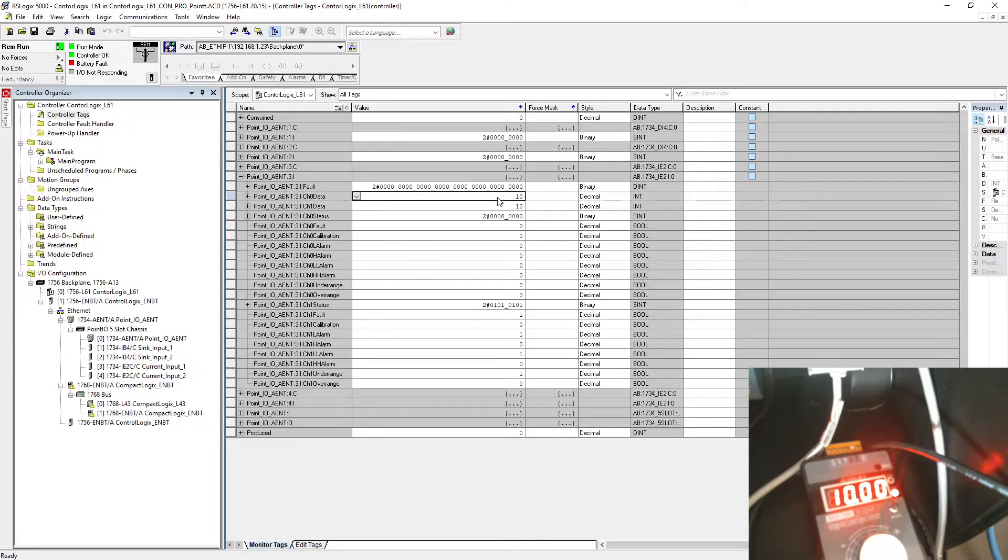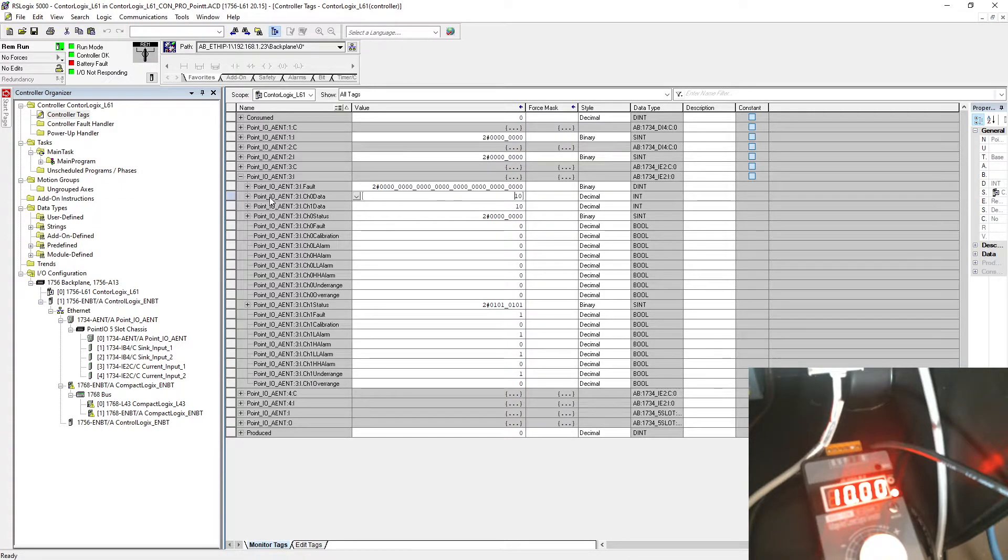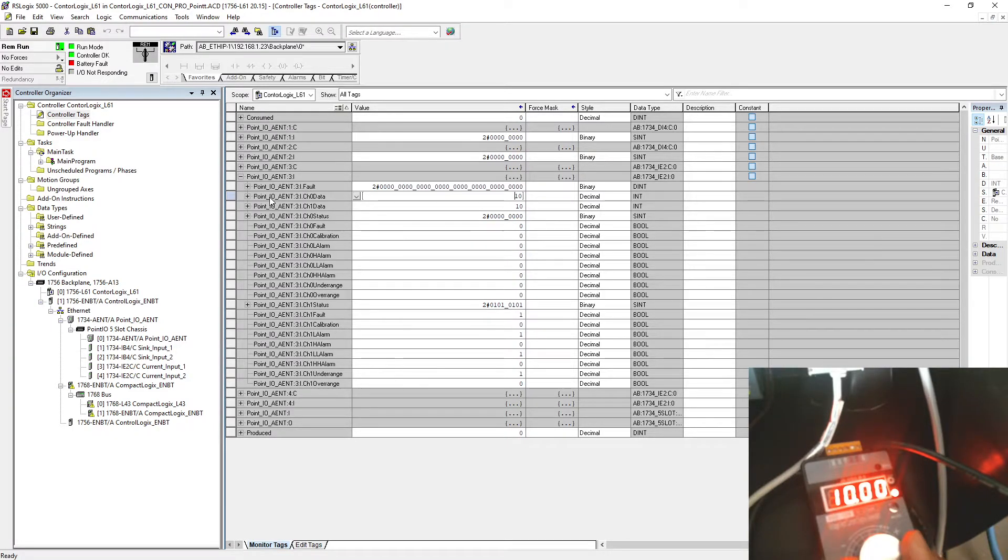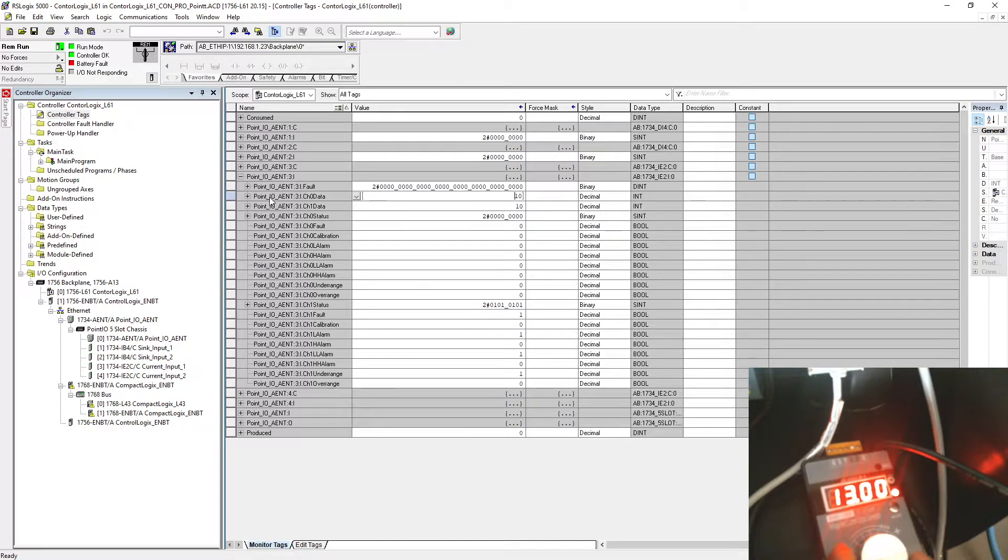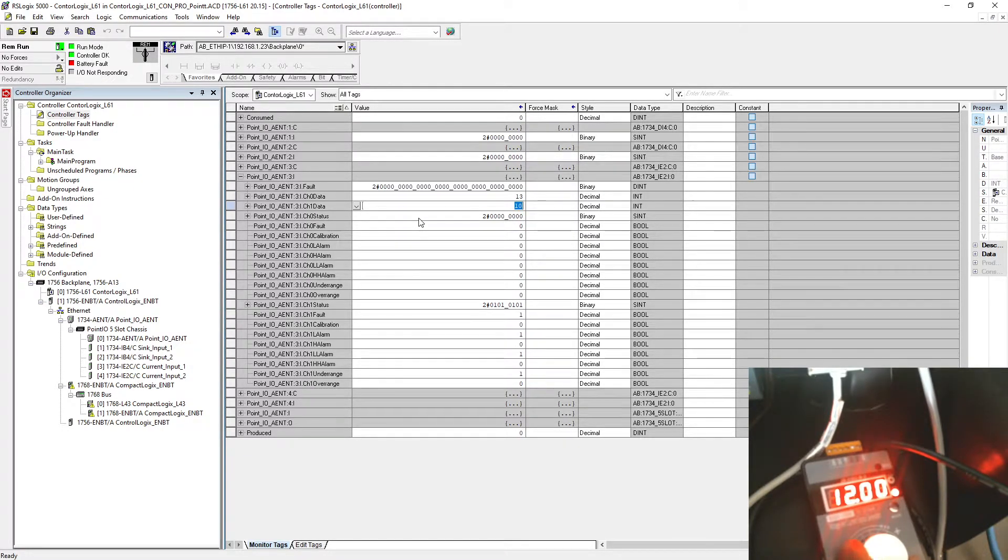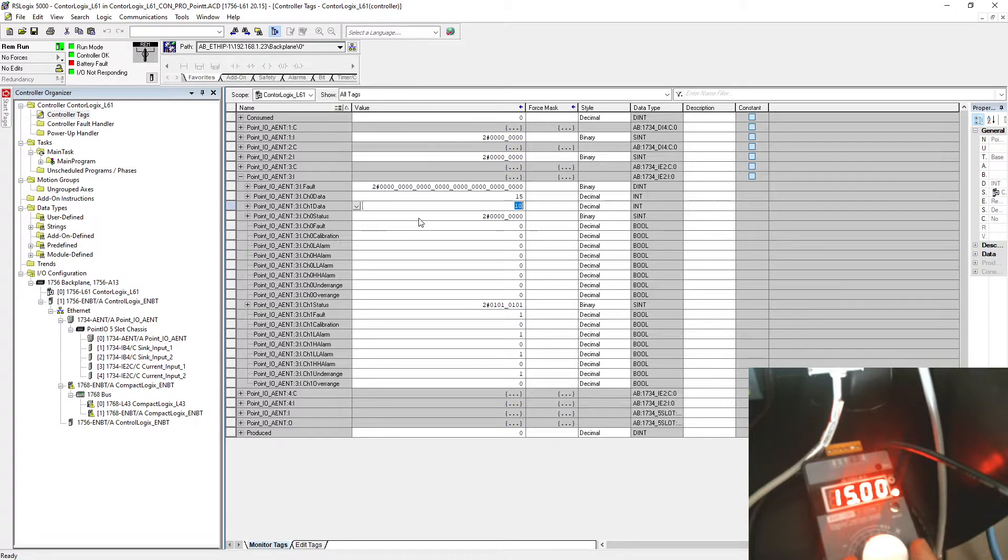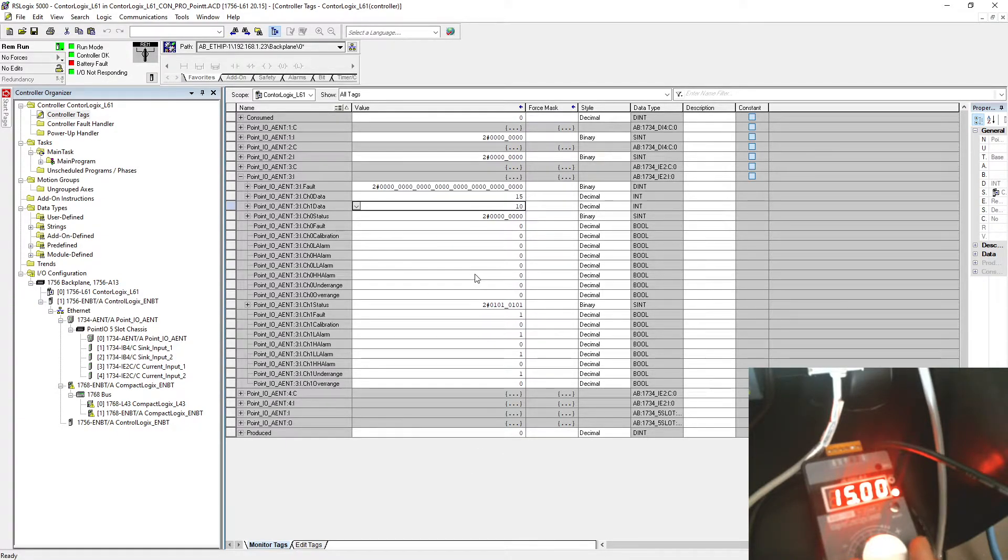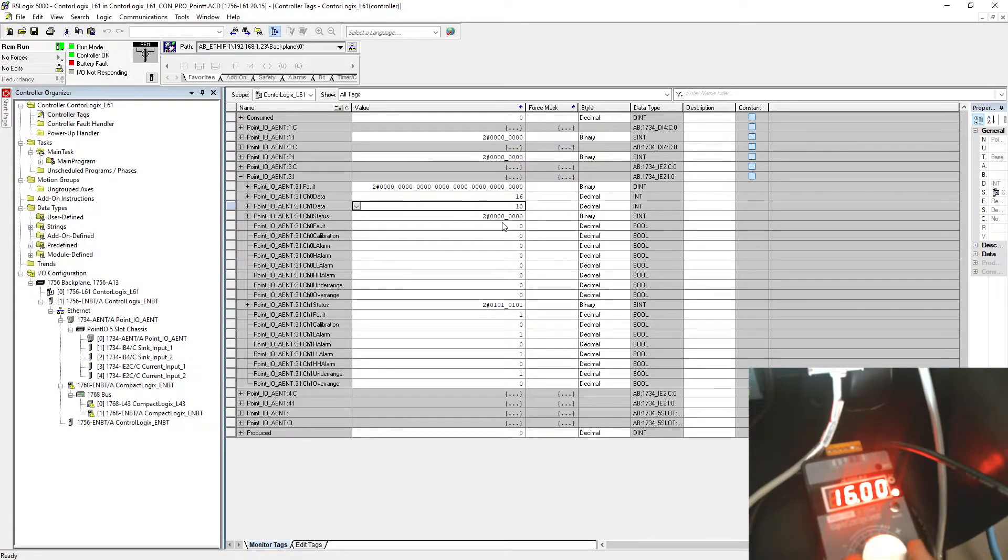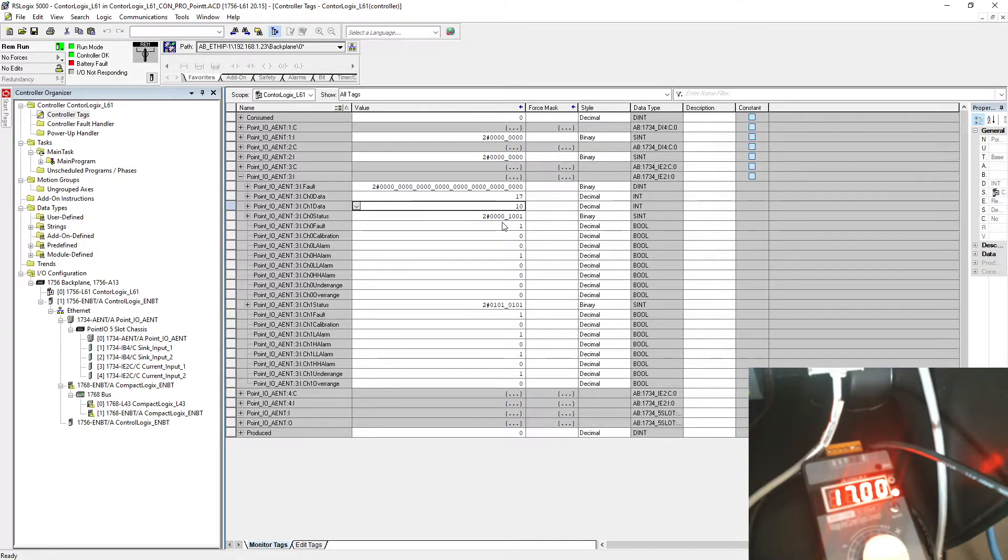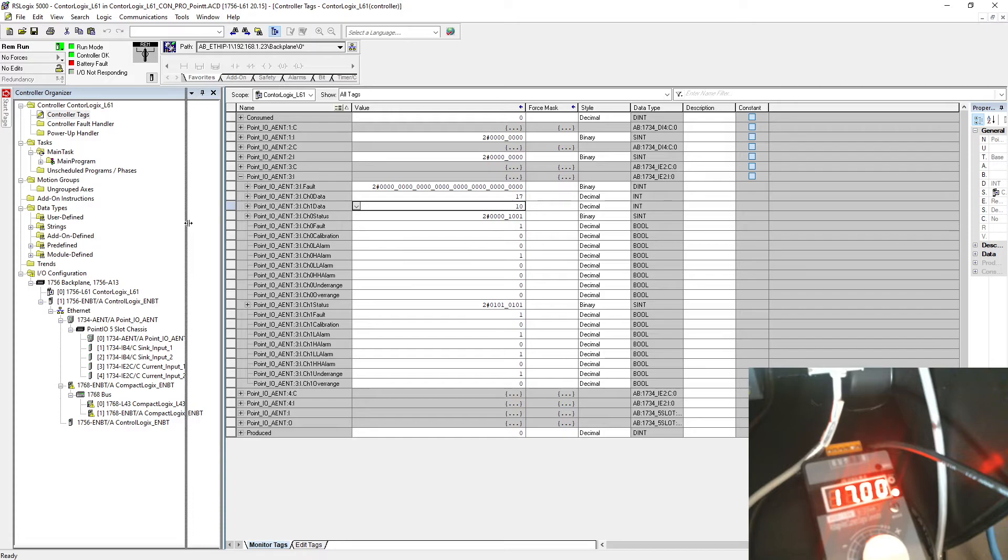Now you can see it's set to number 10, it means it's giving 10 milliampere right here on channel zero. Keep watching this channel zero. When I'm going to increase to 11, it will become 11 over there as well. You can see it's changing with my current generator.